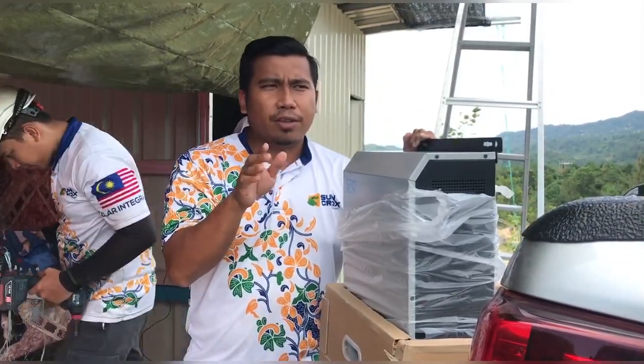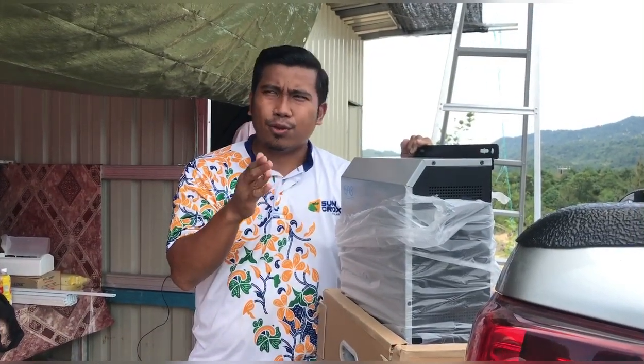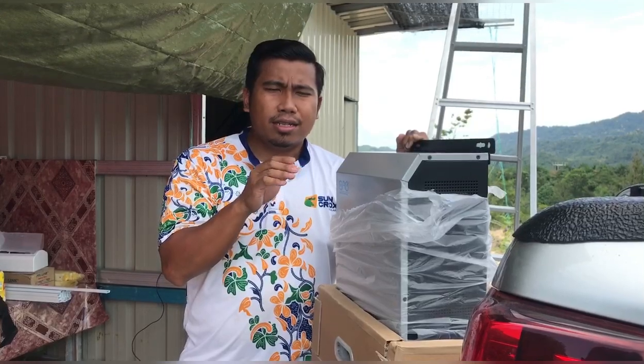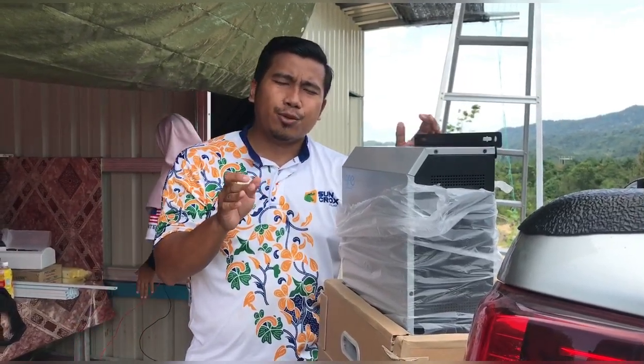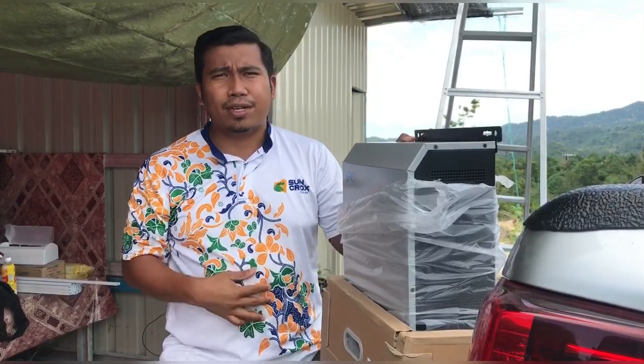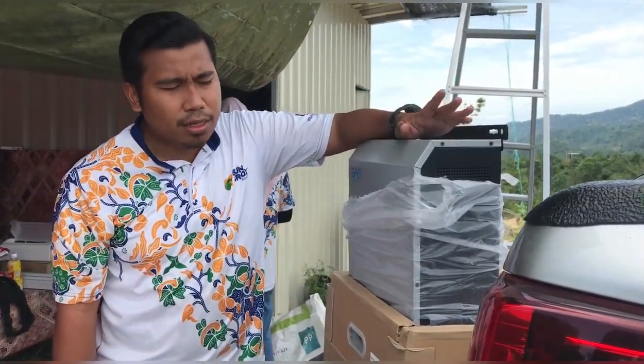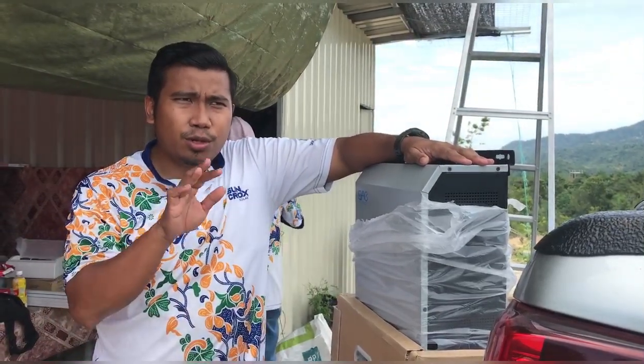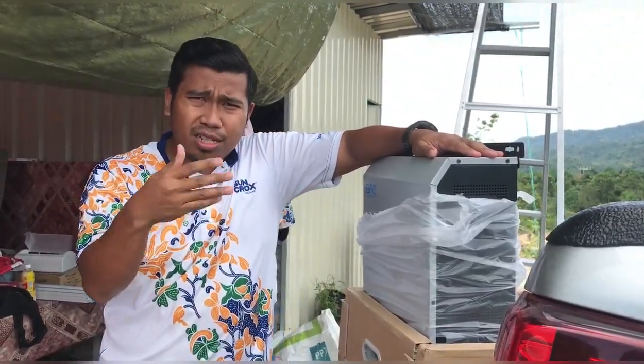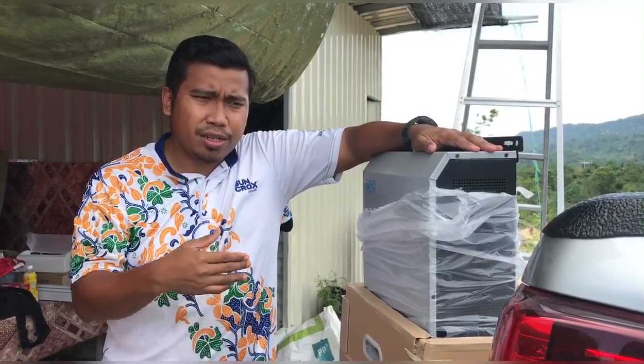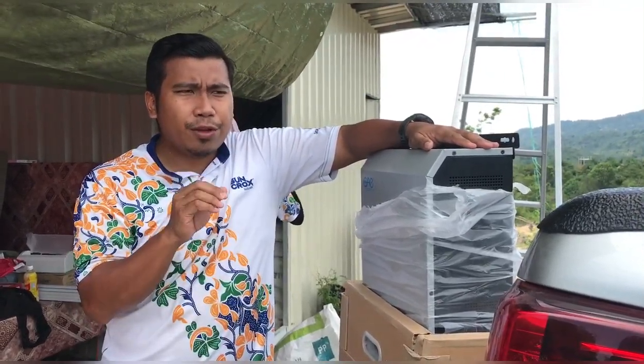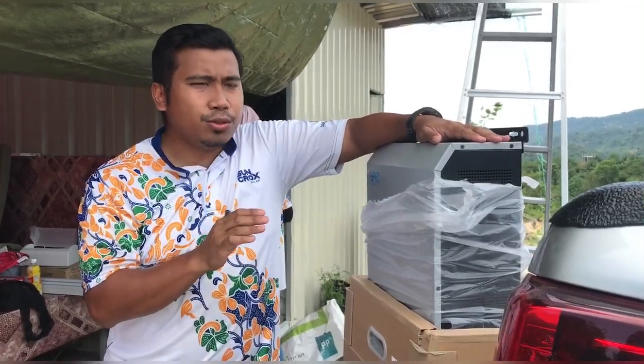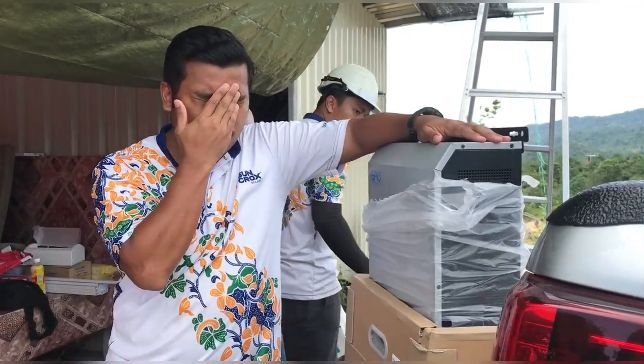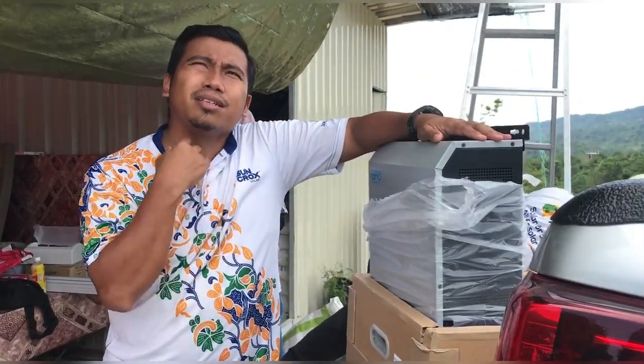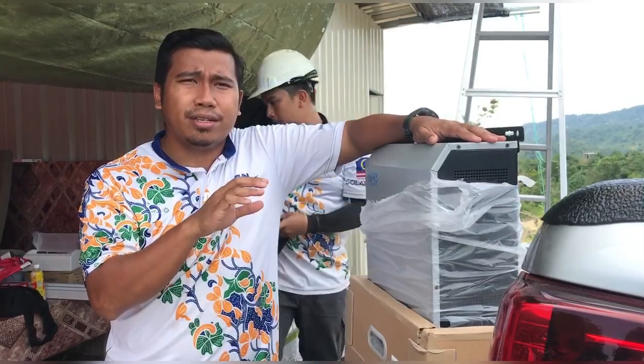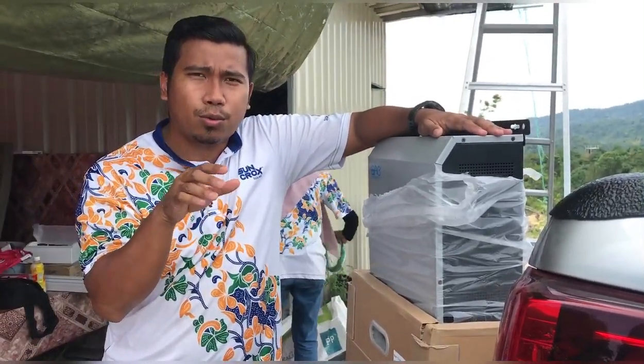So typically, let's say if it's a 1 horsepower pump, 745 watt, 750 watt, the surge will be 3 times. And also the high frequency is not suitable for that kind of application. That's why we need low frequency. The difference between low frequency and high frequency, you can check up on the technicality, but let me give you the practicality. If you have something with induction motor, you must use low frequency because of the surge, and also it can absorb lah. I mean, it can sustain, it can cope with the surge from that induction motor like water pump.